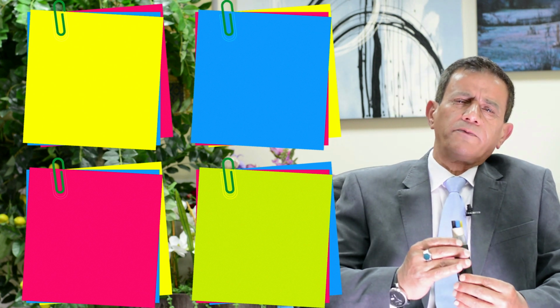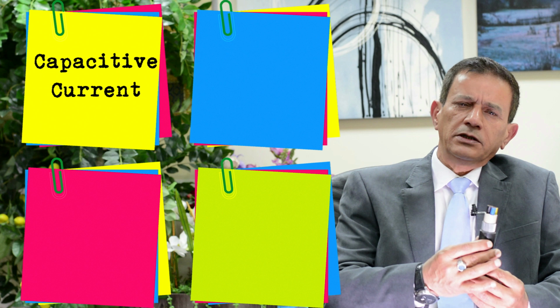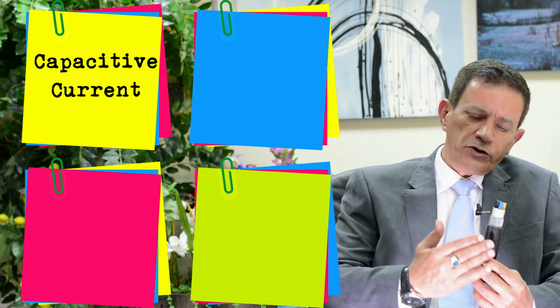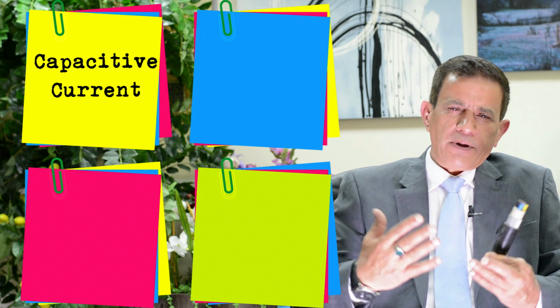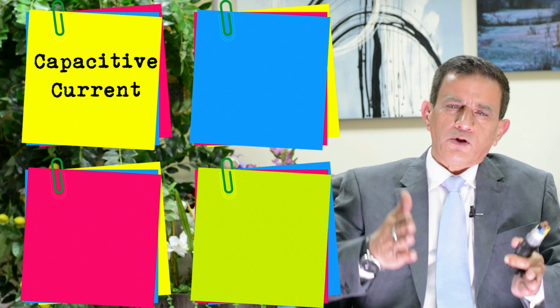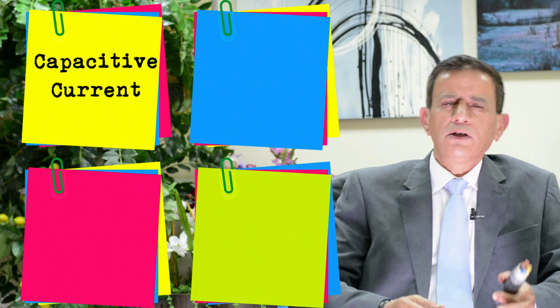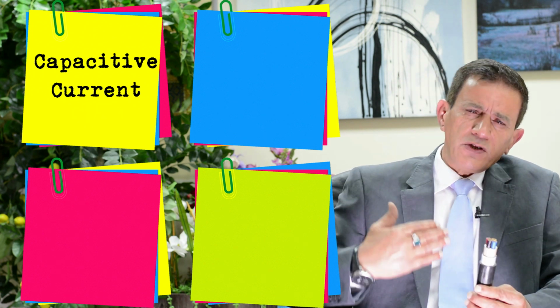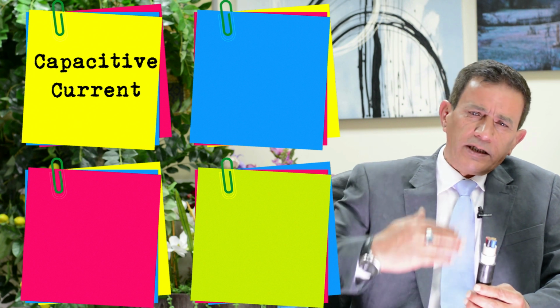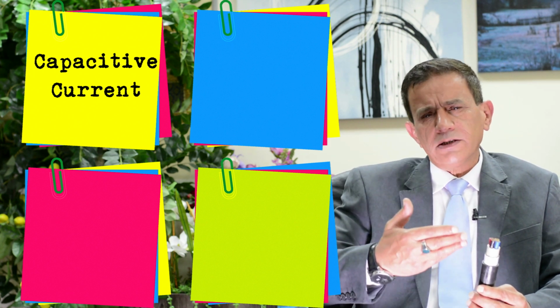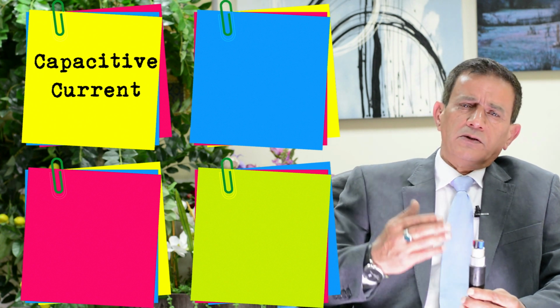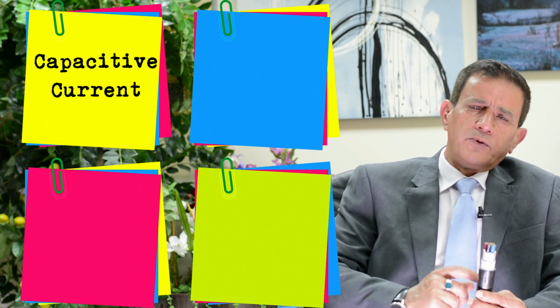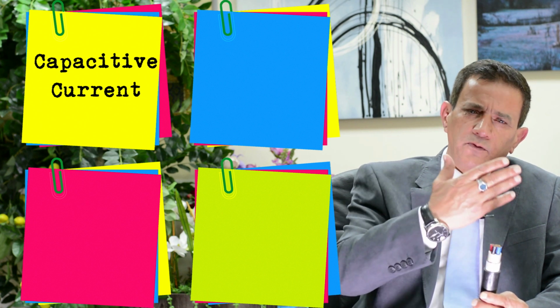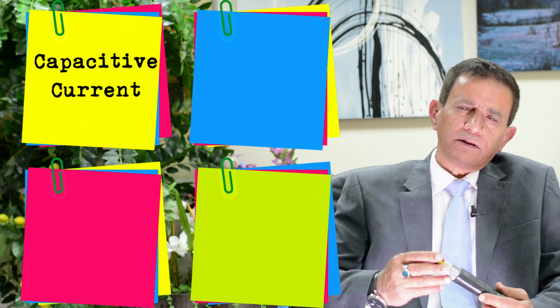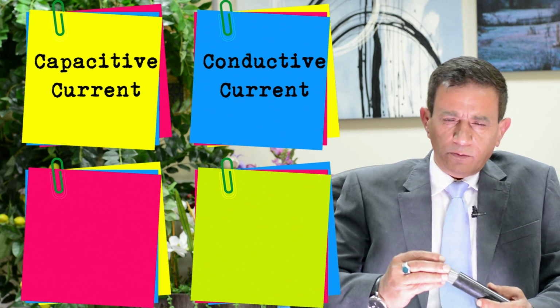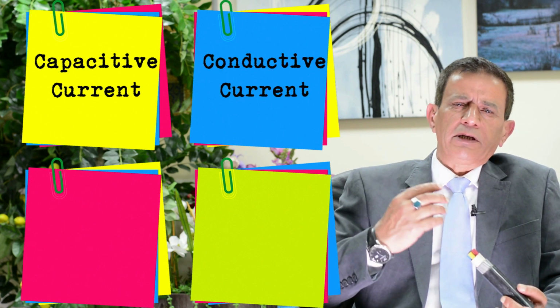First one is the capacitive part. This insulator is subjected to two different voltages from both sides. It will act as a capacitor. Whenever we have a medium enclosed by two plates, each plate with a different voltage, there will be a capacitance. This will be a very fast current. It will rise in almost 10 seconds, and it needs maybe 60 seconds to decay completely. So for the capacitive component, we need to wait almost 60 seconds for this current to decay out completely. Second component is the conductive or resistive component, which applies to any material in this world.